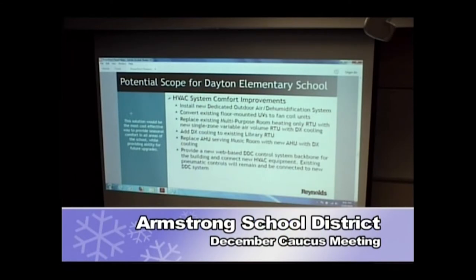Let's say a building the size of Dayton would require 100 tons of cooling for full air conditioning - we would install maybe 40 or 50. So we're not able to cool the building all the way down to 70 or 72 degrees, we're able to cool it to 74 or 75. But bringing it down to 74 or 75 degrees, we're pulling all the humidity out of the air before it comes into the classroom, and it's done a fantastic job cooling elementary schools similar to Dayton, at a fraction of the cost.